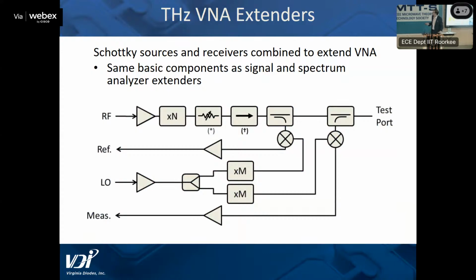We have a cascade of frequency multipliers. We have, in this case, two different down converters. We have one to down convert the signal to sample the signal going out, and then we have another one that samples a signal through a coupler coming back in. We have this on both sides of the device under test. That gives the full 2 port S parameters, both in transmission and reflection, because we know the signal that's going out and the signal that's coming back in. That's mixed down, and then both of those are sent back to the baseband network analyzer at a lower frequency.